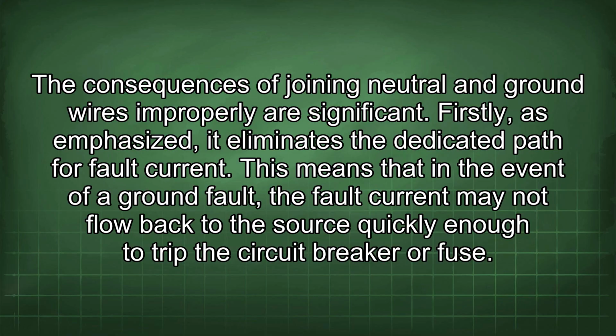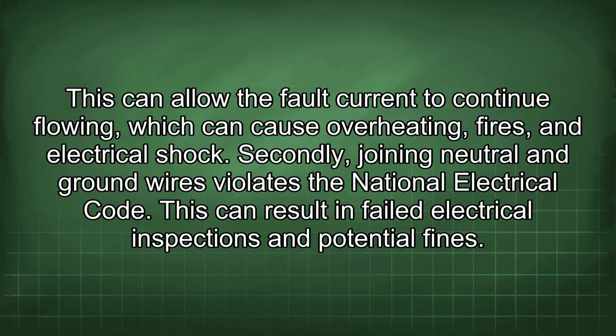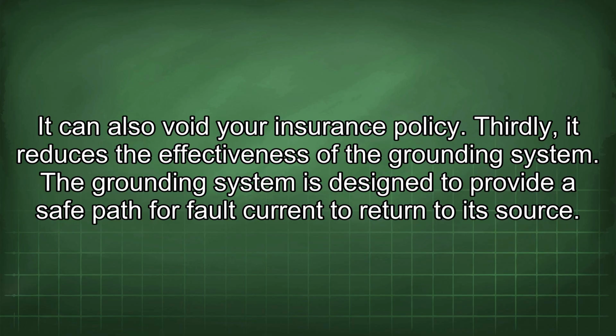Firstly, as emphasized, it eliminates the dedicated path for fault current. This means that in the event of a ground fault, the fault current may not flow back to the source quickly enough to trip the circuit breaker or fuse. This can allow the fault current to continue flowing, which can cause overheating, fires, and electrical shock. Secondly, joining neutral and ground wires violates the National Electrical Code. This can result in failed electrical inspections and potential fines. It can also void your insurance policy.